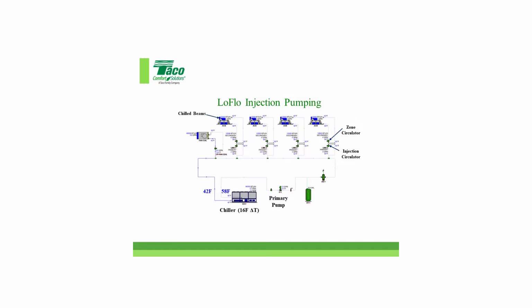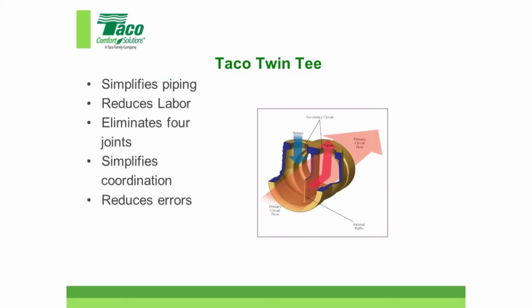This is our low-flow injection pumping type of system. This contraption right here is our twin T. So this is just a fitting, makes installation a little easier, right? And the supply and return going off to the zone is at the same point along here instead of 2 closely spaced T's. It replaces 2 closely spaced T's. That's what that setup is doing right there.